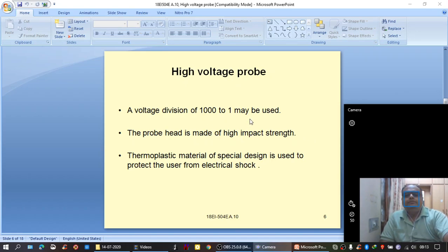If at all the probe's internal divider fails, that results in heavy currents. So the probe head should be in a position to take those heavy currents. Even when the potential divider is working, first this probe head is to be connected to the high voltage portion only. So from there, high current flows to the potential divider where it is converted into low voltage. So naturally, it has to have high strength to withstand high currents. And thermoplastic material of special design is used to protect the user from electric shock.